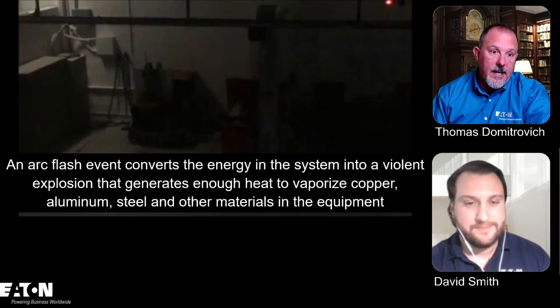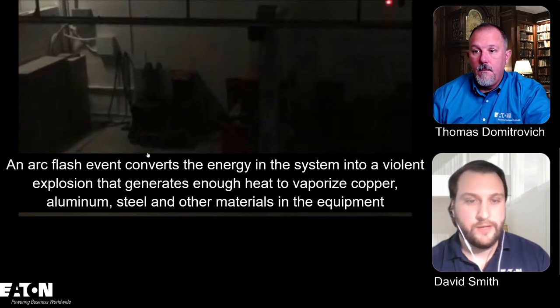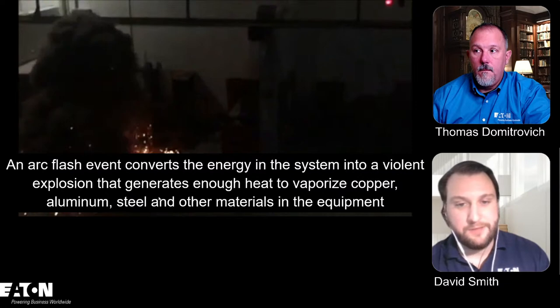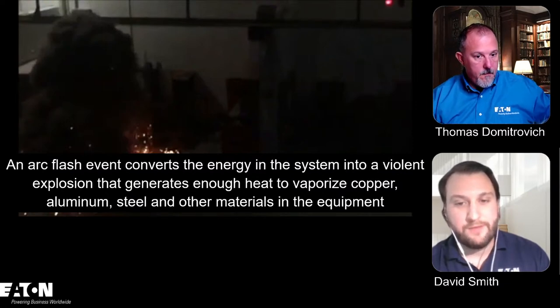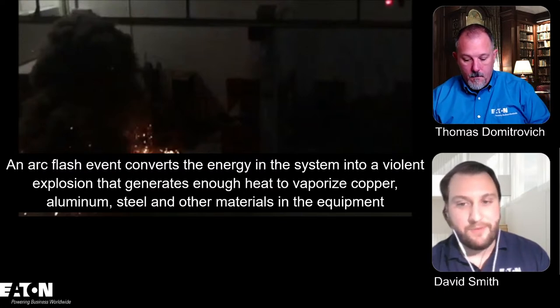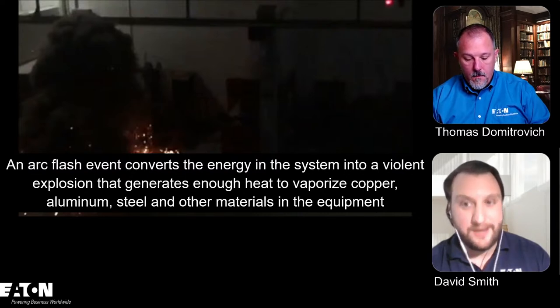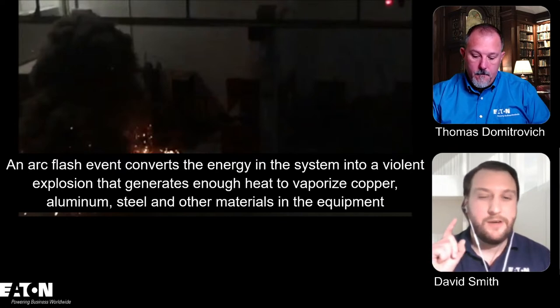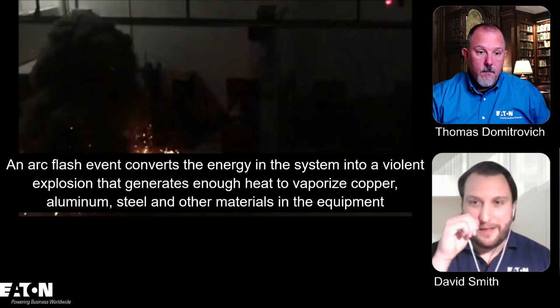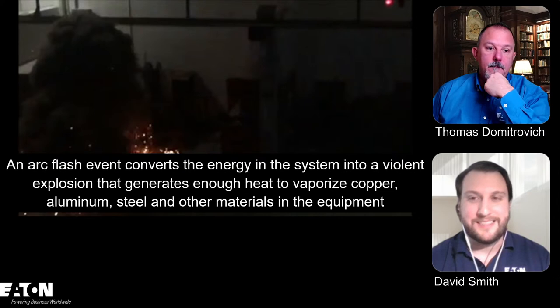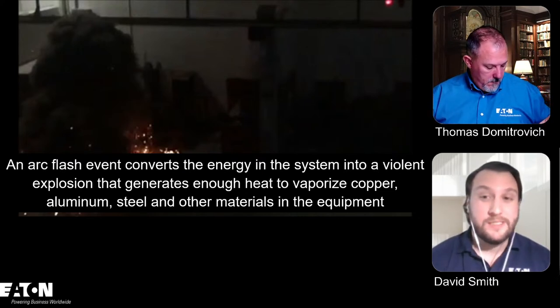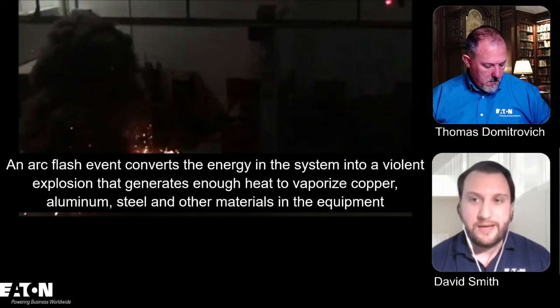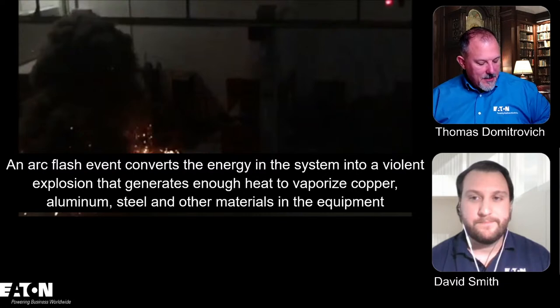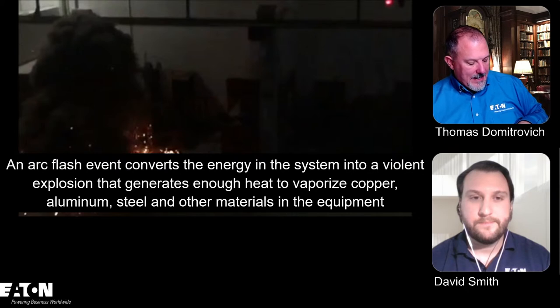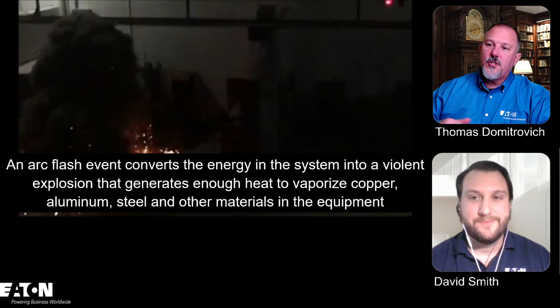Now, I have a question for you whenever you're ready. Yeah, go ahead. I know we're going to eventually go to 240.87(B), but in informational note number four, IEEE 1584-2002, IEEE Guide for Performing Arc Flash Hazard Calculations, is one of the available methods that provide guidance in determining arc current. So arc current is there. It's not defined, but it is actually there, under an informational note. So now we're getting to the style guide and the little things of the NEC, but it is there. Is it defined? Not really, but the good news is that IEEE 1584 is at least listed in the code. So if people are trying to find out these particular values, it is there for you to do a little bit more digging. Yeah. And it tells you it's one of the methods that provide guidance on determining arcing current. But again, it doesn't tell you whether you are determining the maximum or the minimum.